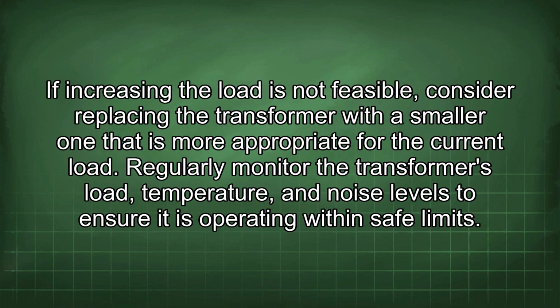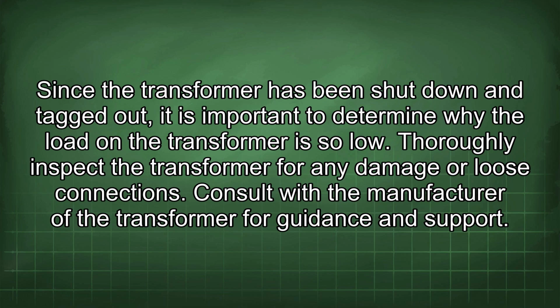If increasing the load is not feasible, consider replacing the transformer with a smaller one that is more appropriate for the current load. Regularly monitor the transformer's load, temperature, and noise levels to ensure it is operating within safe limits. Since the transformer has been shut down and tagged out, it is important to determine why the load on the transformer is so low. Thoroughly inspect the transformer for any damage or loose connections.